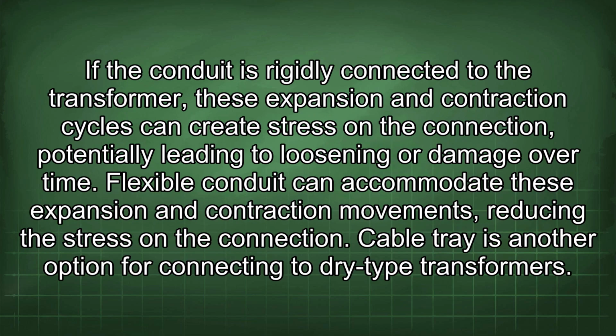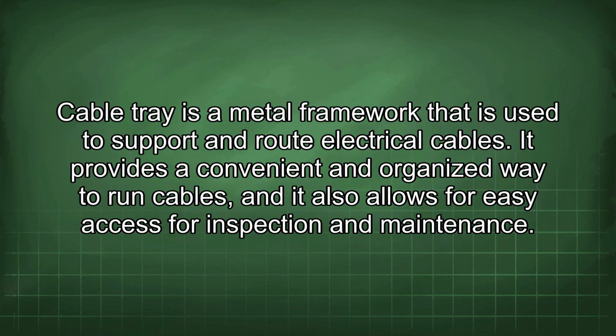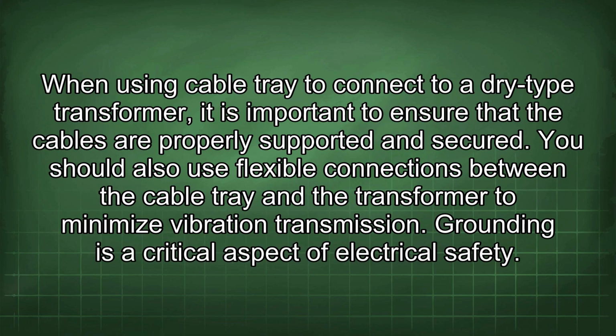If the conduit is rigidly connected to the transformer, these expansion and contraction cycles can create stress on the connection, potentially leading to loosening or damage over time. Flexible conduit can accommodate these expansion and contraction movements, reducing the stress on the connection. Cable tray is another option for connecting to dry-type transformers. Cable tray is a metal framework that is used to support and route electrical cables. It provides a convenient and organized way to run cables, and it also allows for easy access for inspection and maintenance. When using cable tray to connect to a dry-type transformer, it is important to ensure that the cables are properly supported and secured. You should also use flexible connections between the cable tray and the transformer to minimize vibration transmission.